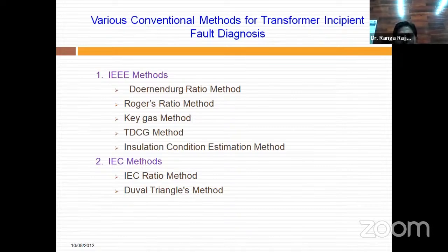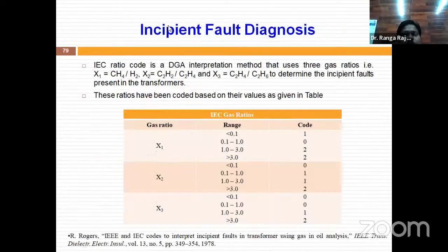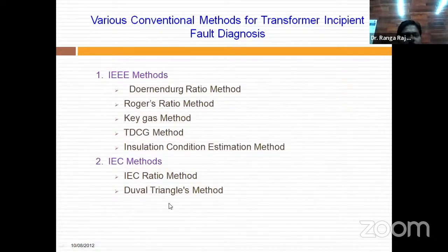Within 5 minutes, I will discuss one small method. So this is one of the methods, the IEC method, the IEC ratio code method. With this method, how the incipient fault is determined, that is the object, okay.